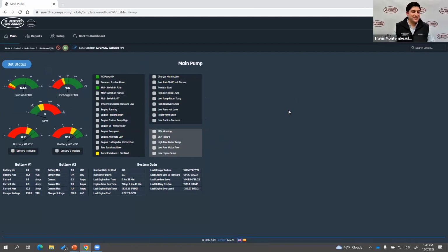Yeah. So the piece that is probably missing from this is the ear, the nose, and the eye test effectively of somebody in the room still. When we start to talk about things like remote testing and remote monitoring, because with fire pump controllers right now, you can schedule your automated test. In that controller, you can say, start a weekly test for this diesel at this time every week, and if all things are okay, automatically shut it down after that 30-minute test. That's okay to do. Code will allow for that.